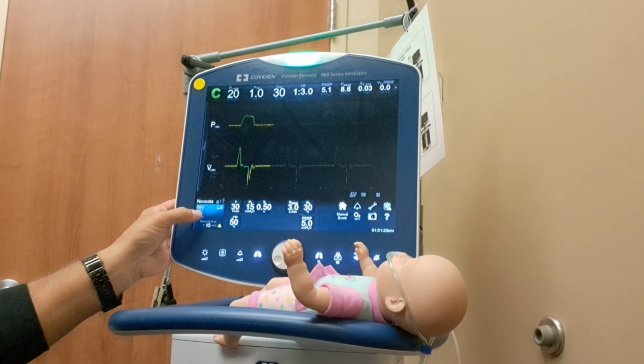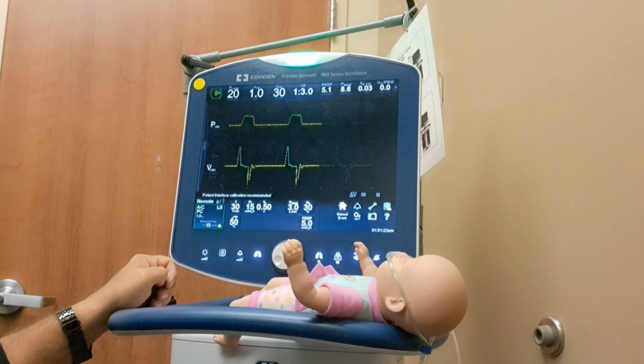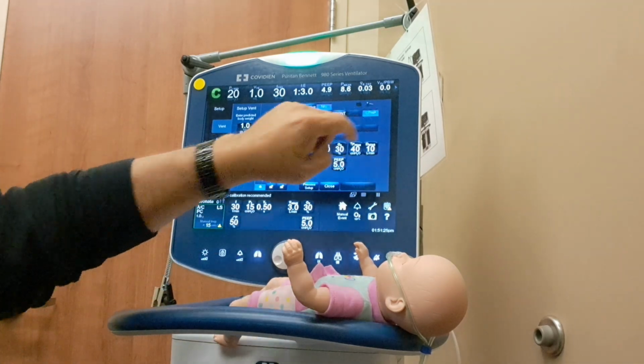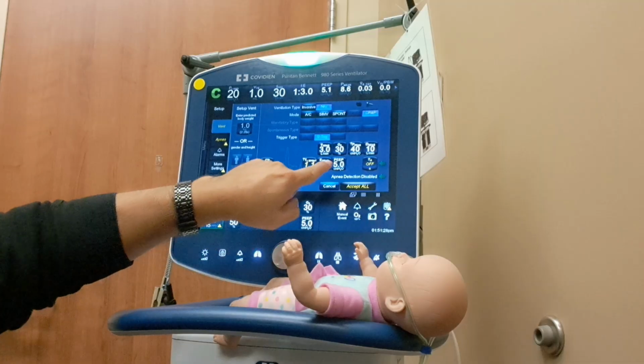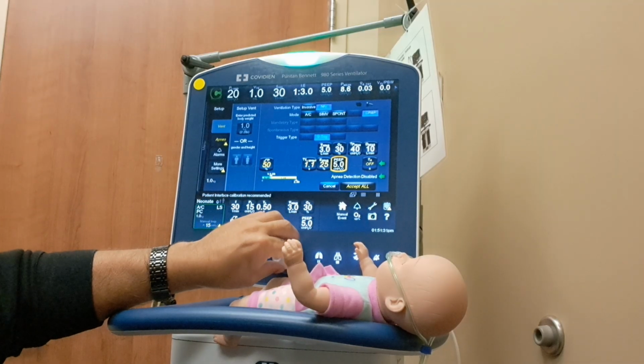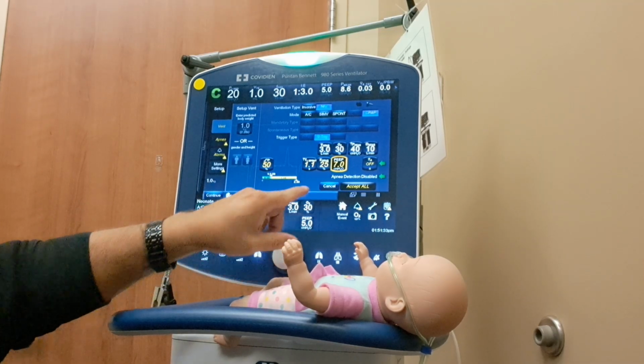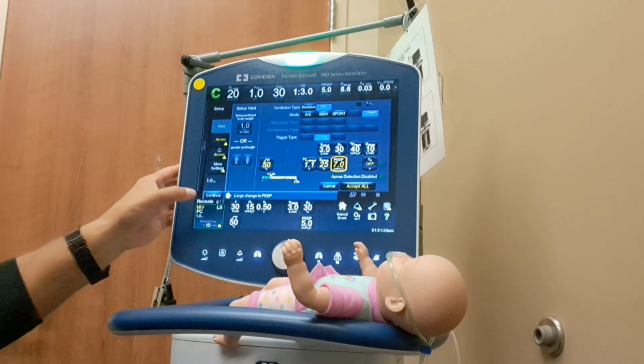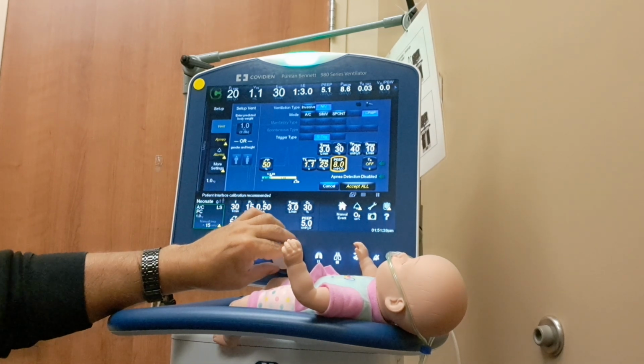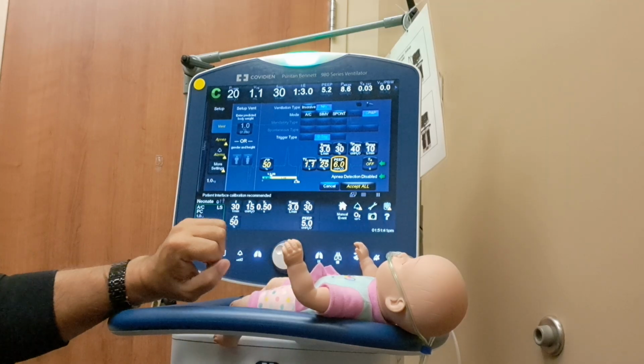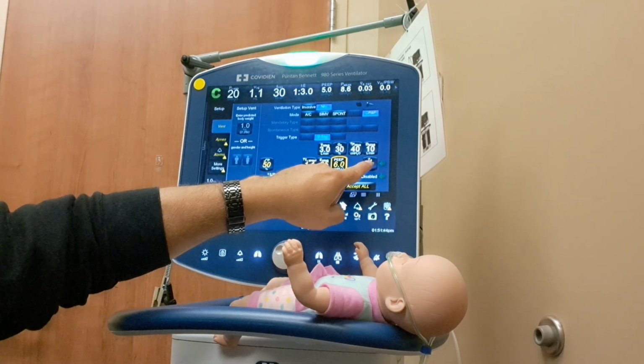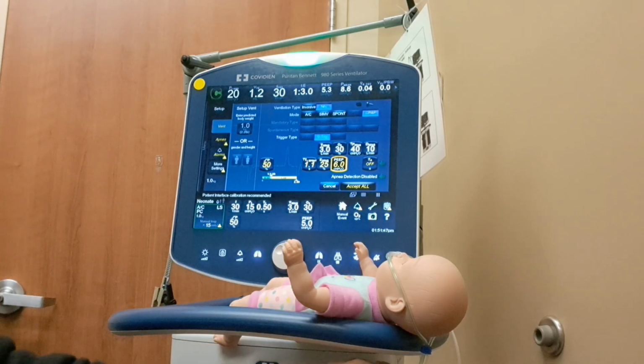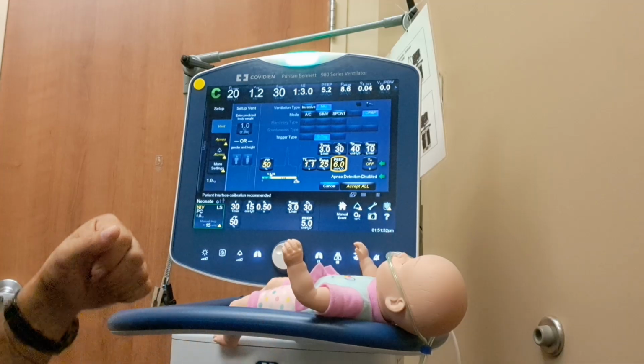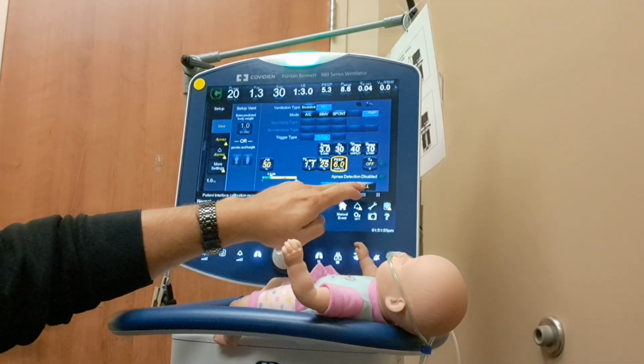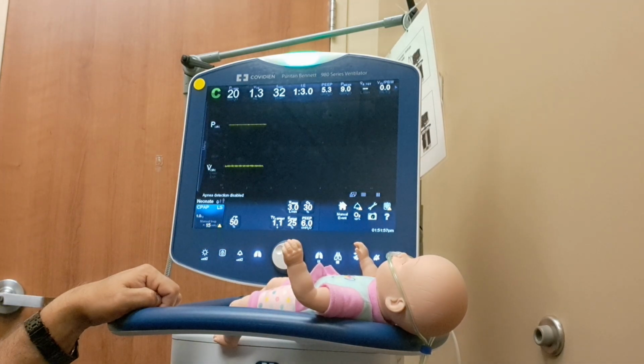Again, in the lower left-hand corner here where your mode is at, select that. We'll go to CPAP. Dial in whatever CPAP that we want. If you go 2 above, it says large change in PEEP. Just acknowledge, say, yep, I know that. And you could go higher if you want to. Let's just say we want 6. This right here is alarming to tell you apnea time is off, because a lot of times in CPAP, because we're using an interface, it can't sense spontaneous respirations. So we'll leave that off and we'll accept all. And so now we're just in CPAP.